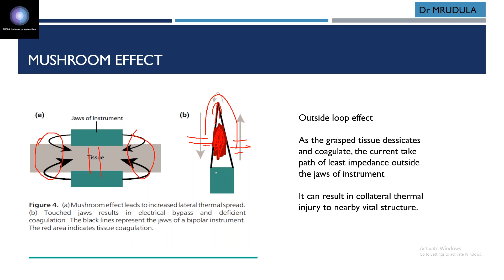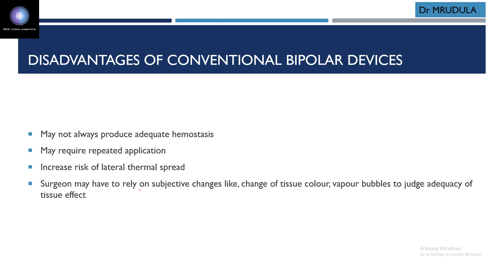Disadvantages of conventional bipolar devices: they may not always produce adequate hemostasis, may require repeated application, and increase the risk of lateral thermal spread because of repeated application. See, actually bipolar will decrease lateral thermal spread, but with repeated application, it increases the risk of lateral thermal spread. The surgeon may have to rely on subjective changes like change of tissue color and vapor bubbles to judge the adequacy of tissue effect. So to overcome this, advanced bipolar instruments have come.